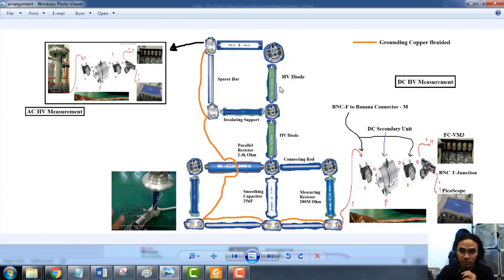Here we use two high voltage diodes, the green one, which function as a rectifier. The blocking voltage for one unit is 140 kilovolt, so with two diodes in series it's approximately 280 kilovolt.